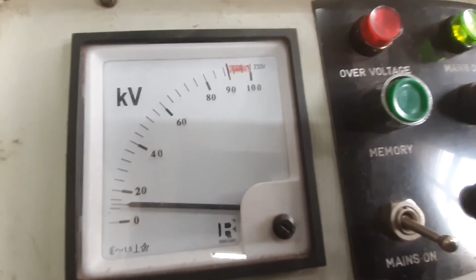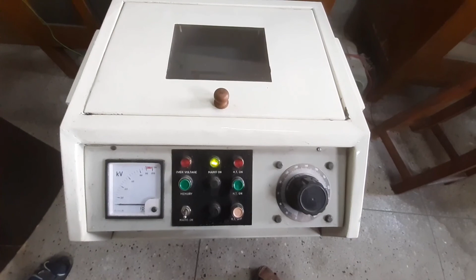So at 30 kV, this oil is punctured. By this way we can measure the dielectric strength of liquid insulating material like transformer oil. So this is your one experiment, and we will explain it in detail later.